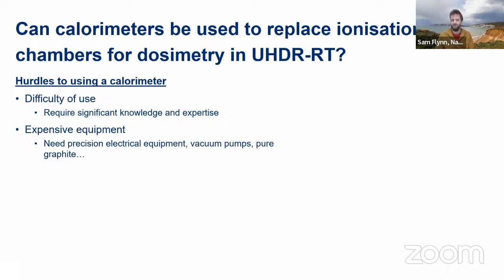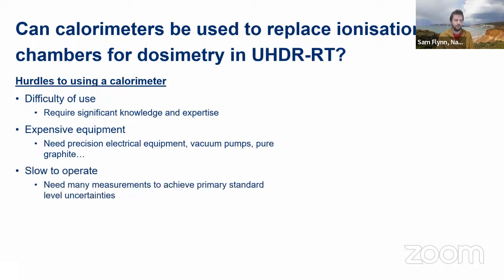So it becomes impractical for a clinic to have its own calorimeter. It doesn't really make sense. They're also quite slow to operate. An ion chamber can be used within several minutes of getting out of its case, whereas with a calorimeter, you're looking at an hour of measurements for most. And that's considered fast. It's an hour for us after setup to do an energy in a certain modality. If you're using a water calorimeter, you're looking at half a day at least.